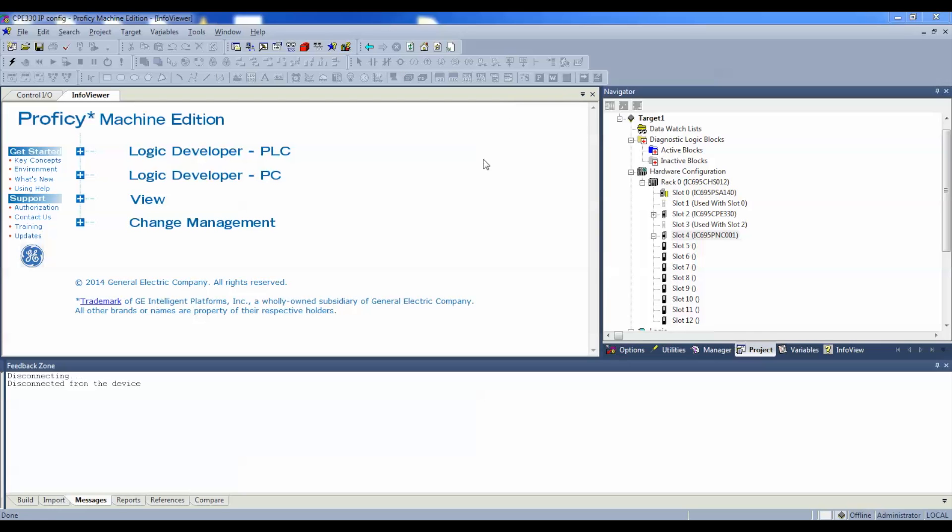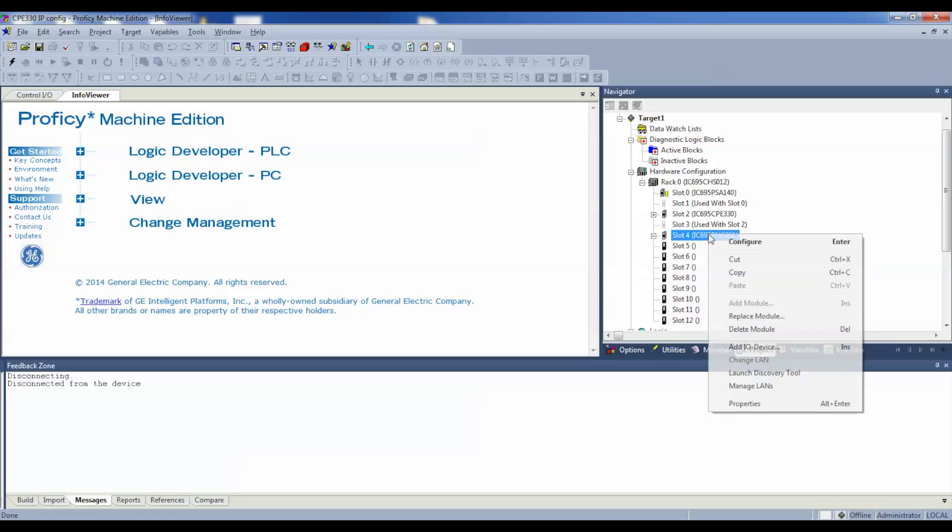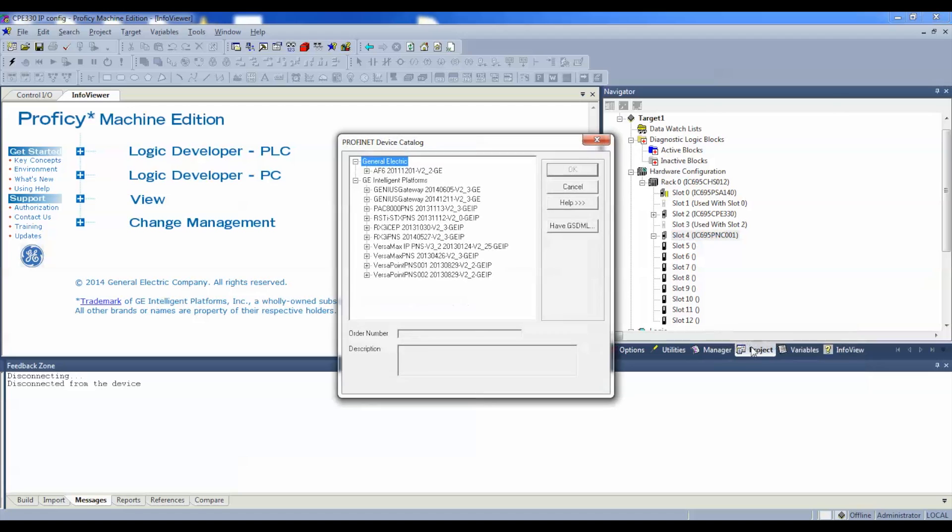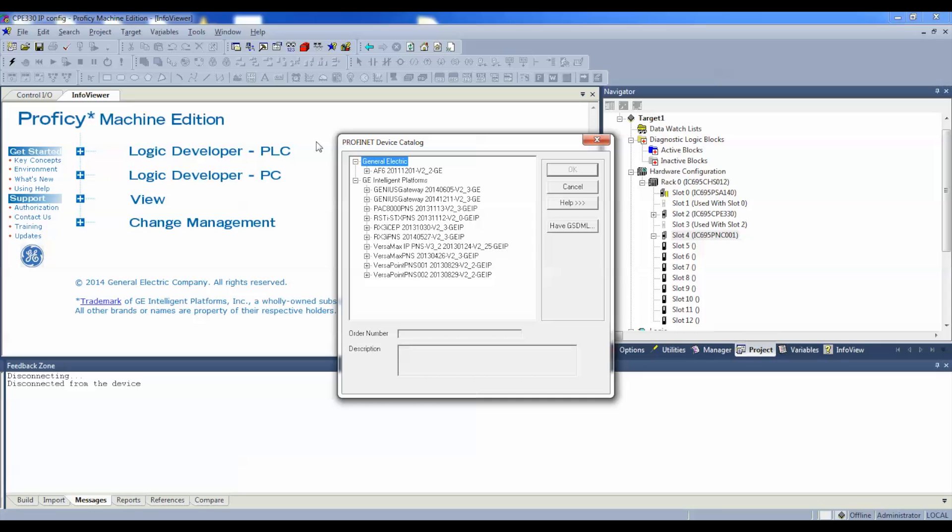Now, what I'm going to do is right click on the PNC, and I'm going to go down in this window to add IO device, and this is where I find my Genius Gateway communications. Now, what you would do is after you've downloaded the GSDML, you want to click here where you see my arrow, and then go through and browse to find that file, and download it to this file. So that when you actually do the processor download, it will download to the processor and allow this whole system to work. And I'm also going to give you an example of if you've skipped this step accidentally.